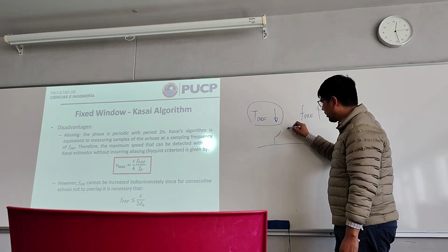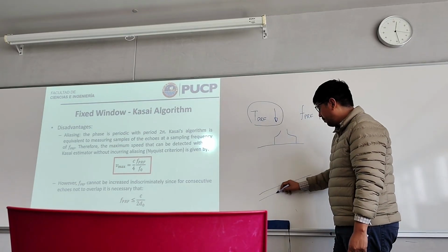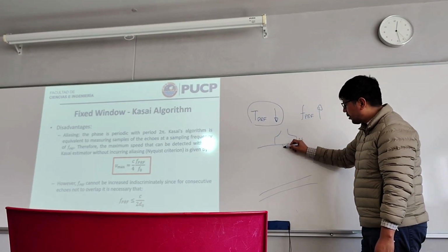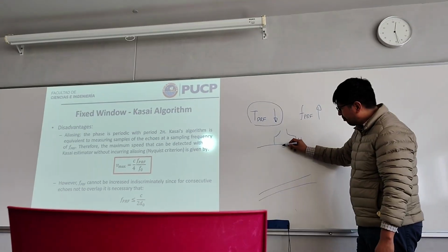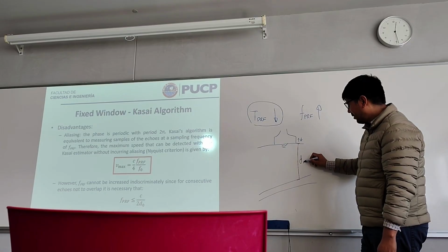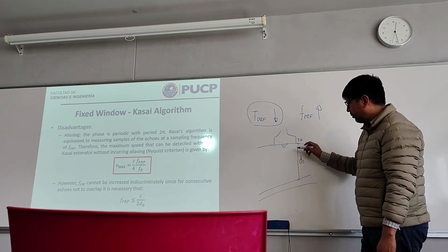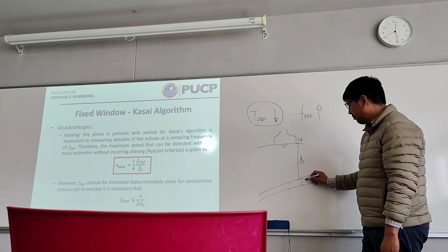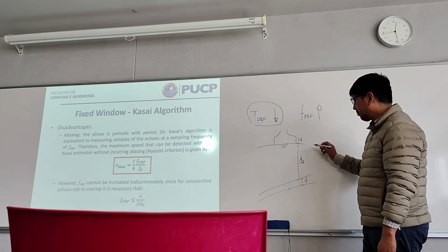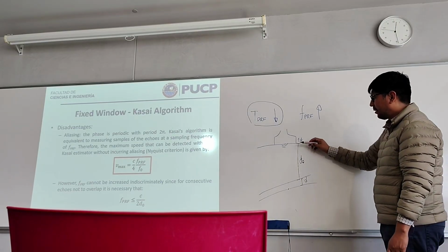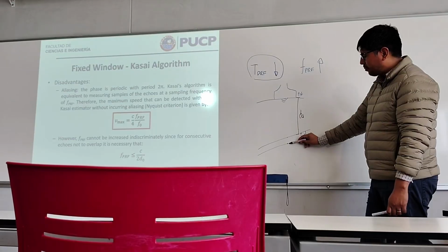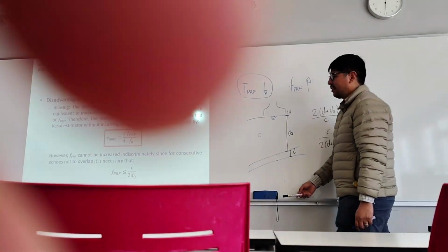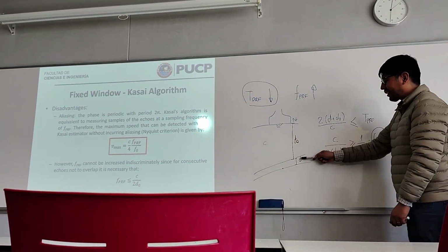But if this is very small, the problem is that we have the transducer and we have some vessel. When we send the first pulse, we need to wait at least the time to reach the vessel, and even the last part of the vessel. If the vessel has some thickness, we need this echo to reach the last part of the vessel and then go back. So the total distance is really D0 plus the thickness of the vessel.